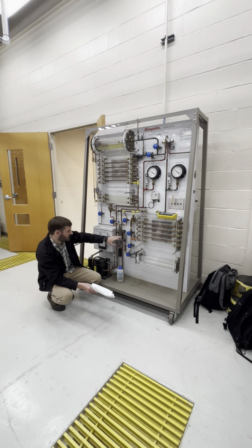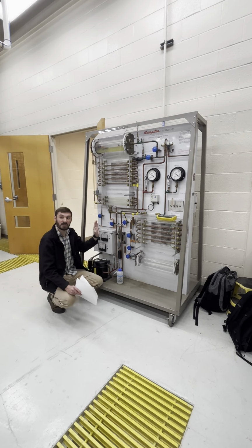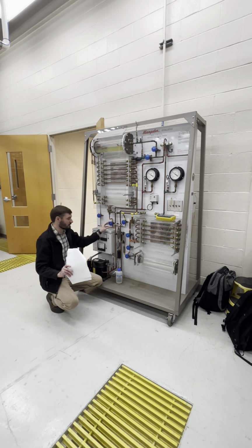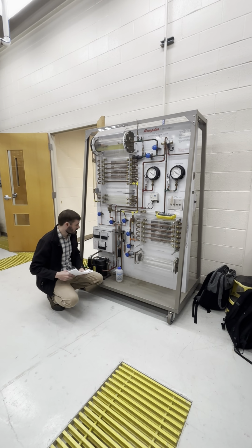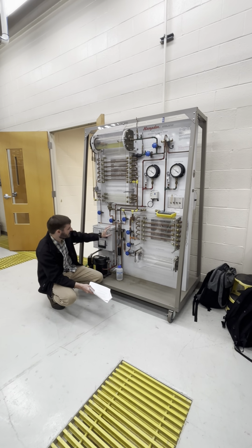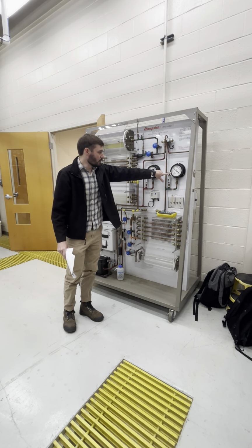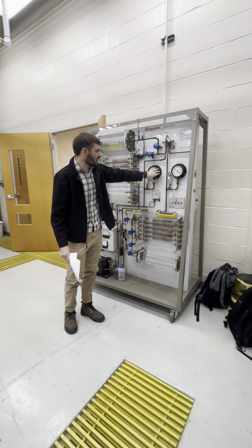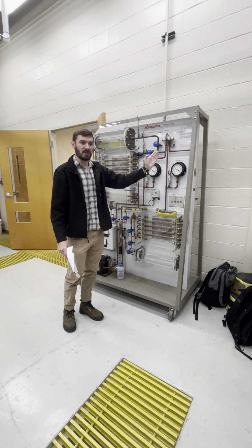Eventually, it's going to drop down, and then we can slowly open it a little bit more until we get it fully open. We want to get it fully open. That way we're not influencing the system with the valve, we're just letting it do its own thing, okay? But once you finally get it open, then you can let it run and get to steady state. At some point in time, your two pressures, your discharge side, which should be positive pressure, and your suction side, which should be a vacuum pressure.